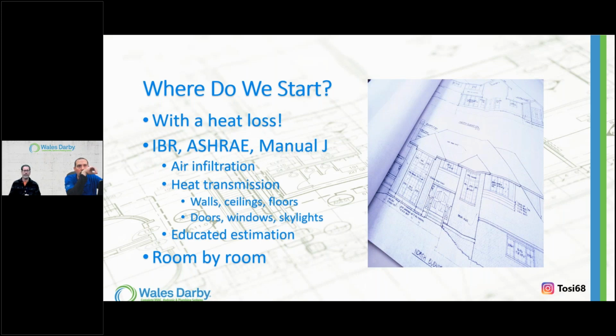The boiler's already double the size you need for the load of the house. That's what you want to figure out. That's where you really want to put the pen to paper, do a heat loss, and figure what the envelope requires. Then you go to the source, and you go, wow, that is grossly oversized. And then you go to the emitters, and again, that's grossly oversized. So that tells me one of two things. Either get the tin snip out and start cutting fins off, or I'm going to take this perfectly good cast iron boiler out, and do something different.